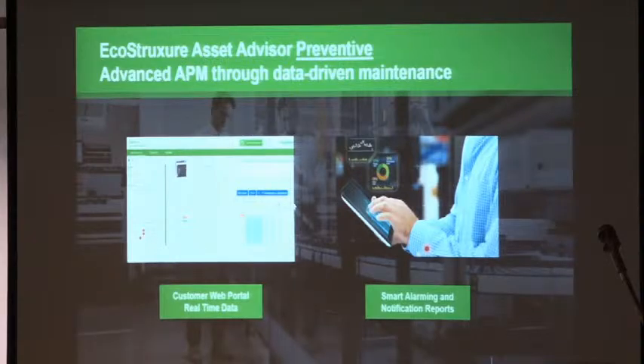In this first tier, the preventive tier, we provide customers with real-time data monitoring of their assets through a web-based portal along with mobile applications, to monitor every time how their assets are performing. We can also set different alarms on the performance of these assets, so if we detect an imbalance in one of the phases of a low voltage circuit breaker, we can automatically inform the facility manager through smart alarming about the abnormal condition. This tier is based on smart alarming and real-time monitoring of the information.